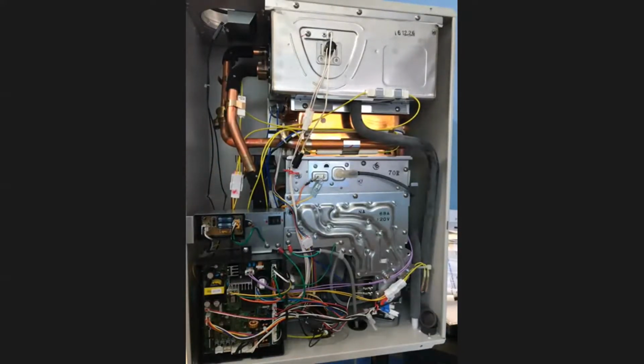Mark sent in a question on the side: domestic hot water mixing valves. I'm a fan of a domestic hot water mixing valve anytime we're using something like this. It's not actually required in this unit from the manufacturer. It's never a bad idea, but it's not actually required because we have that internal bypass valve in there that is adjusting for that. So it's a little different animal. One of the things, and Mike's put it there in the chat, is the Noble combi, and it works a little different because it's doing space heating and domestic hot water, and it can switch back and forth. And that's where you get into, hey, I really want to have that mixing valve just in case I spike in my temperatures as I'm shifting.